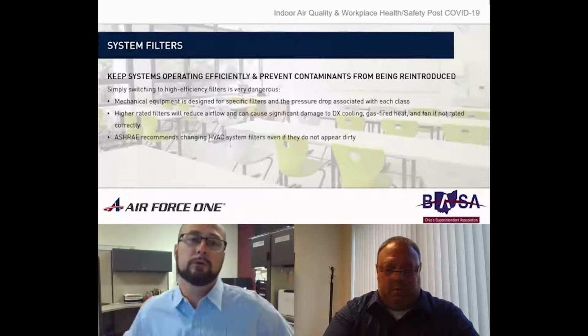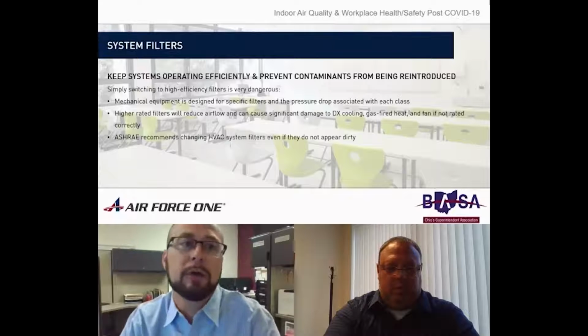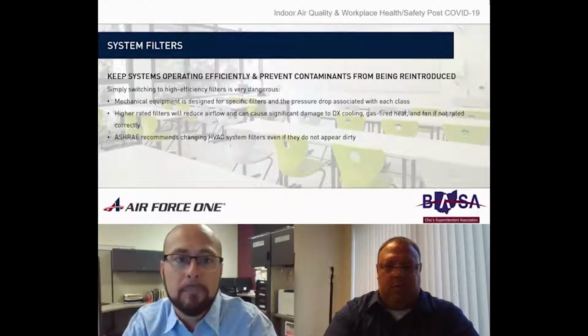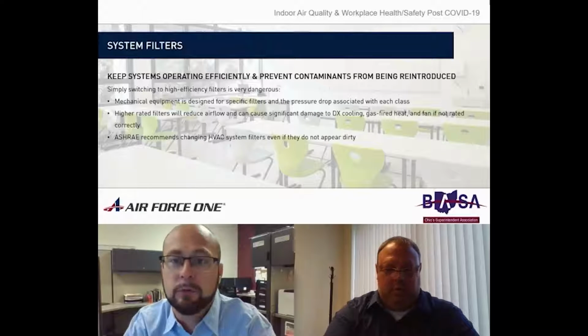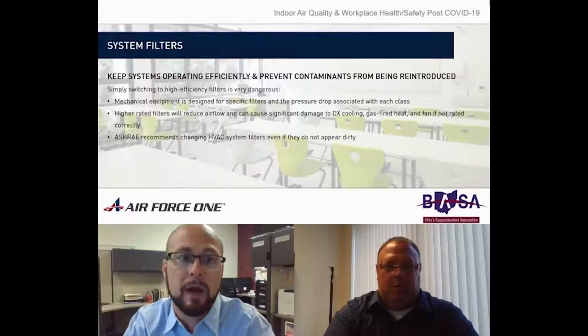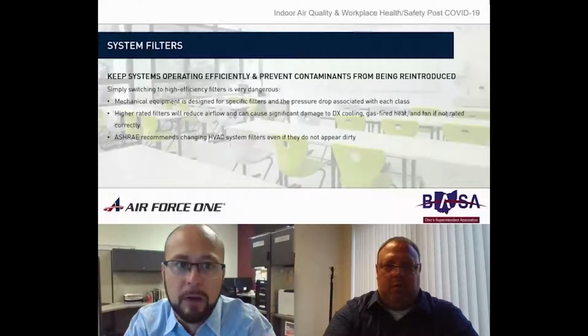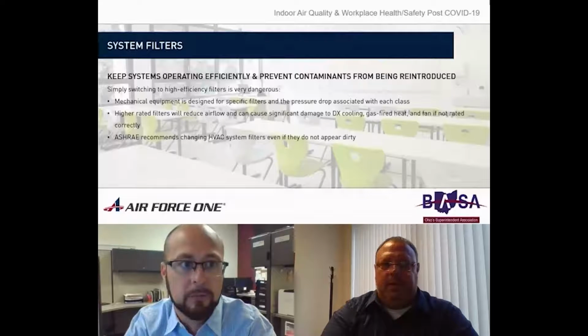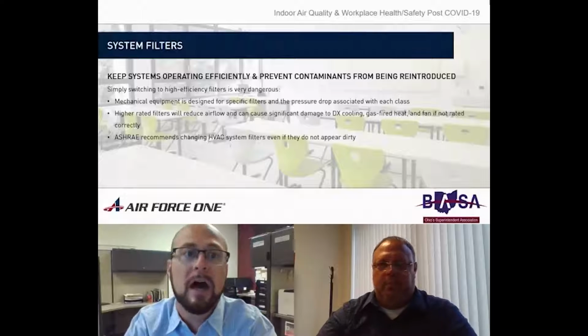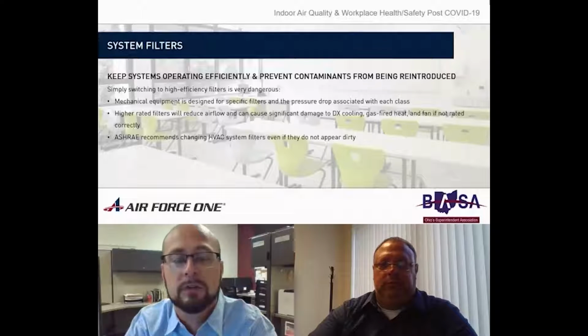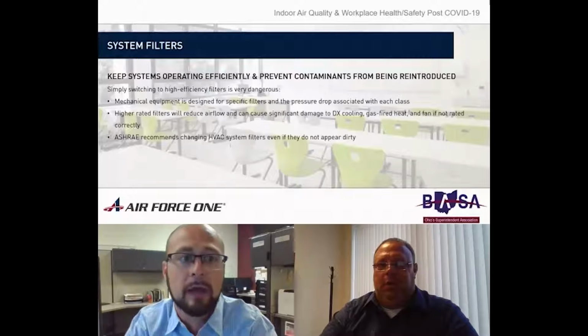So system filters, and there's a lot of differing opinions and misinformation about system filters out there. So it's definitely something we want to address. System filters keep your systems operating efficiently and prevent contaminants from being introduced into your system. But simply switching to high efficiency filters is very dangerous. And we'll elaborate on that shortly.